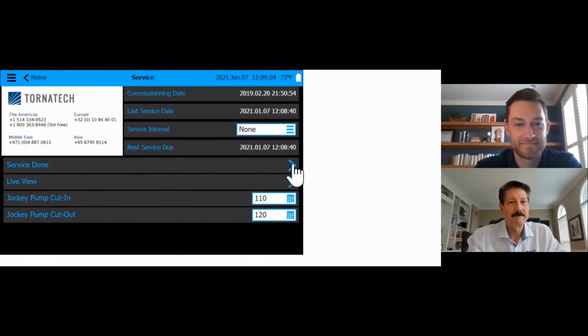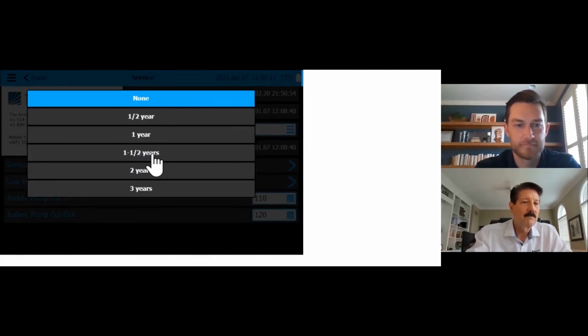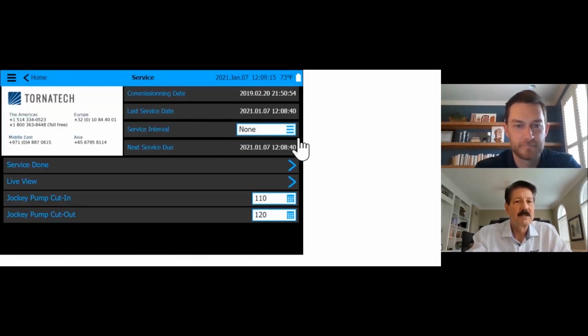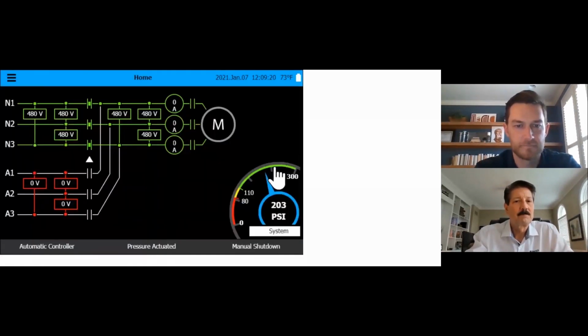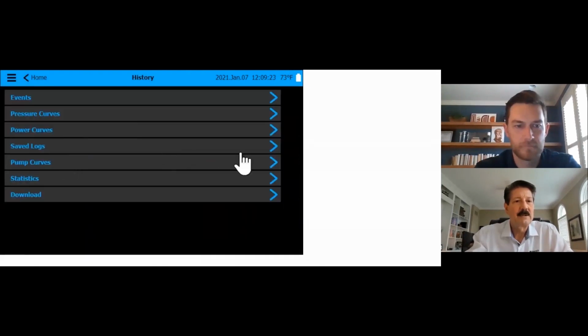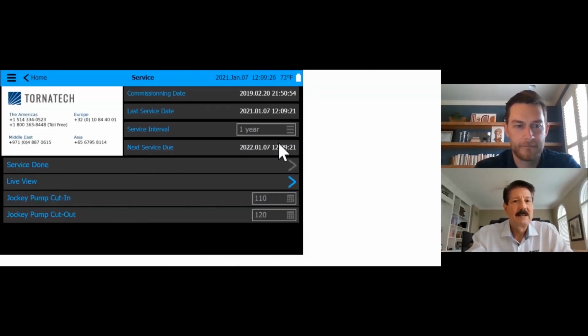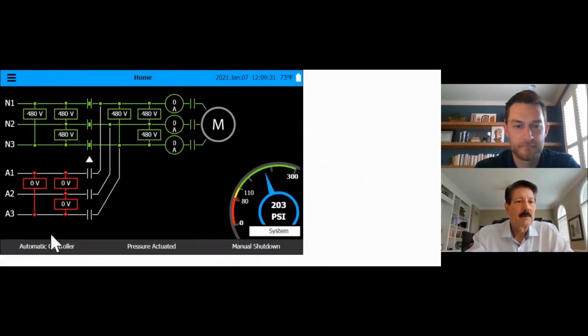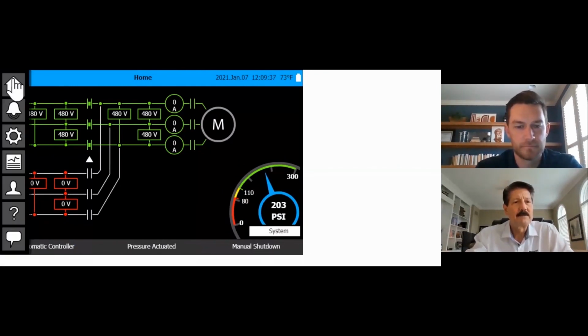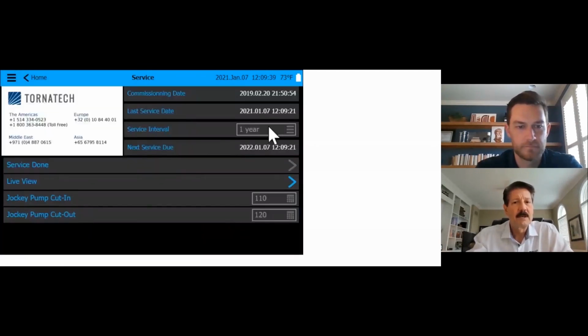So service. What I could do is service intervals here. Last service date was this date, which I clicked. I can literally set it up for 6, 12, 18, 24, 36 months. And if I set this up for, say, a year, and I hit service done, I go back to the screen. In 1 year from today, I will have a yellow alarm coming across the bottom of the screen that says service required. So it's a good way to track if you have specific requirements that you need to do, you can have it set up that way. It's quite nice.